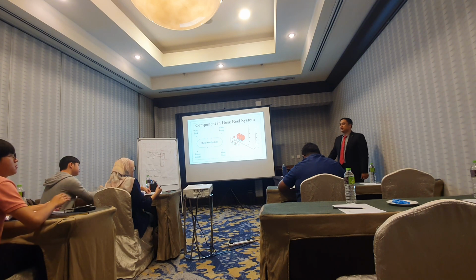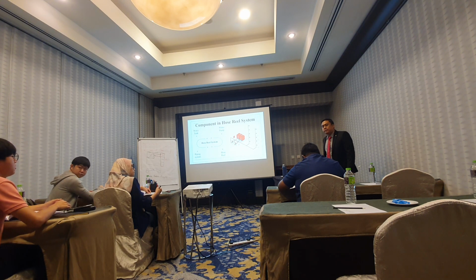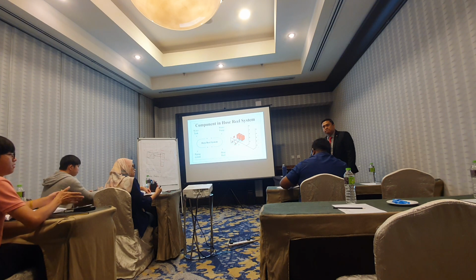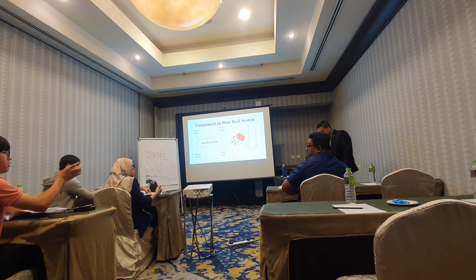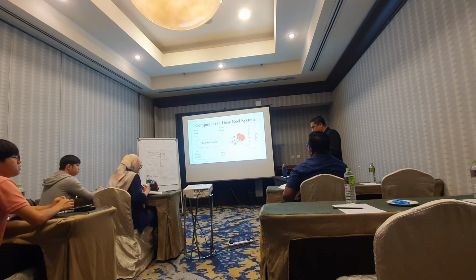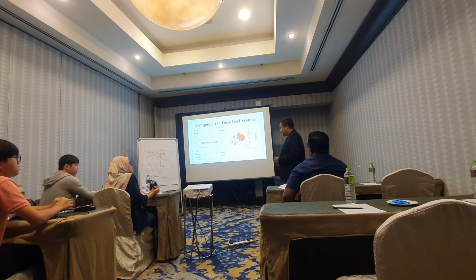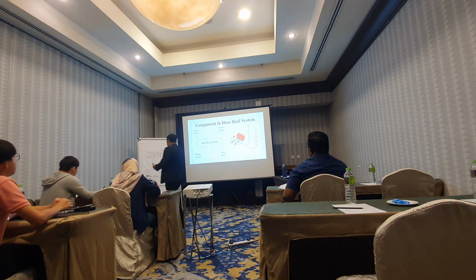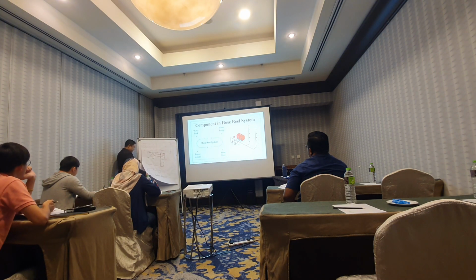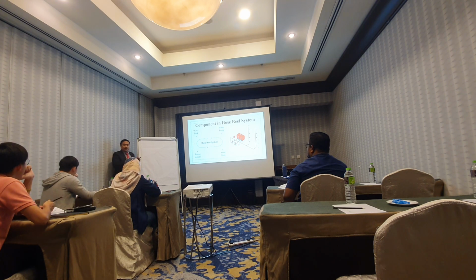Okay, dia soalan yes. Tanya ada satu standard macam apa sistem multiply to tank, macam satu tank multiply 2. Boleh. But then it's not for hose reel only lah. That is the case where you have a sprinkler system with hose reel system at the same building. Maksudnya bila ada sprinkler, of course sprinkler is varies lah, depends on what type of the building and what is the OH you use and how high the building is.